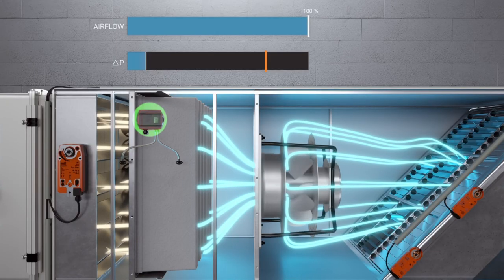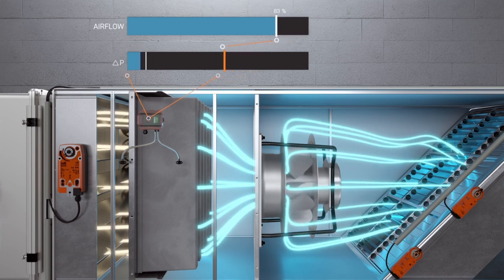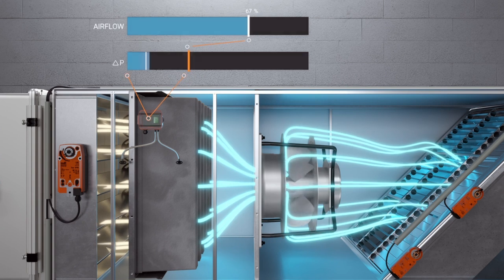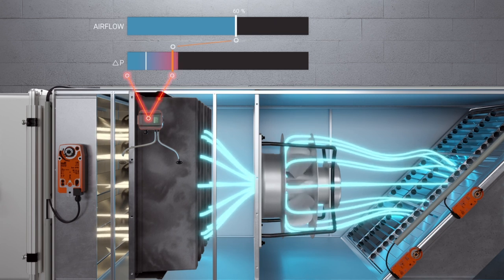So, we see that if the air handling unit is controlled as required, a differential pressure switch is not suitable for monitoring the filter. In these partial load operations, the differential pressure must be measured continuously in order to reliably assess the condition of the filter. This requires a differential pressure sensor instead of a differential pressure switch. A differential pressure sensor continuously measures the pressure drop through the filter, even when the air handling unit is at partial load. Depending on the measured volumetric flow, the final differential pressure also changes dynamically. If the differential pressure exceeds this limit value, a necessary filter change can be reliably indicated.